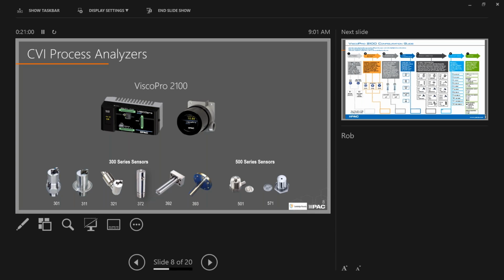The 372 is what we call our flow-through sensor. So there are 6 millimeter ports on each side, and the fluid actually flows through the sensor. There is a water jacket available for this if you wanted to thermally control the temperature. And this is very beneficial where the process volume is low, such as Pat mentioned with the optics industry, when they only have about 8 liters of process fluid and the lines are low. In medical coatings as well. In medical coatings, yes, thank you.